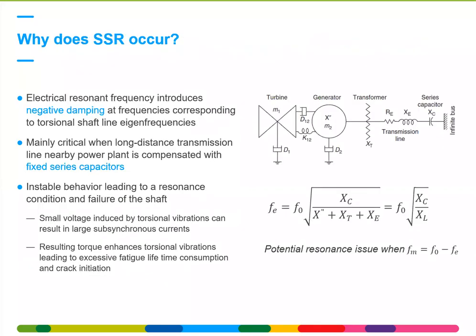So we will now detail more the SSR, subsynchronous resonance. And the most simple example is given on the right. You have a shaft line which is modeled by two inertias coupled with a spring. So for instance, your gas turbine coupled with a generator. And then you have on the right the grid, which is modeling just the transmission line and the series capacitor bank. By implementing the series capacitor bank, the grid on its own gets a natural frequency.